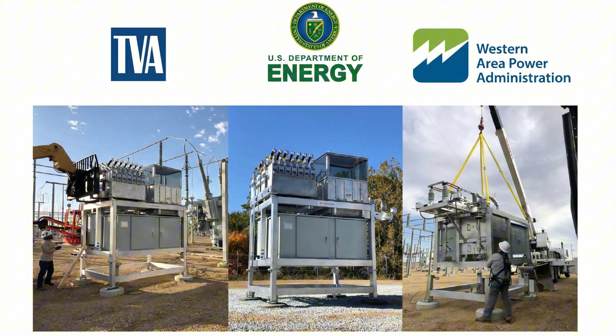The industry claims that they will have time and notice from the Space Weather Prediction Center to shut the grid down. We saw this week that NOAA, the Space Weather Prediction Center, predicted a G4 level storm to hit Earth, and their predictions were off—they missed it by about half a day. Those three neutral blocking devices in the US grid started to activate many, many hours before the predicted effects on North America. What that means is we cannot predict GIC.